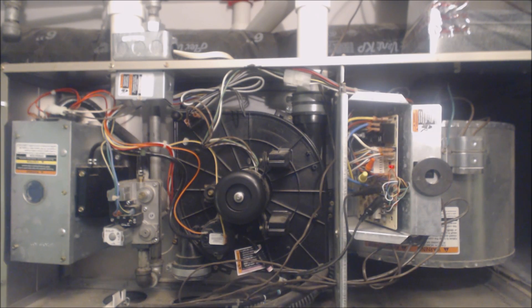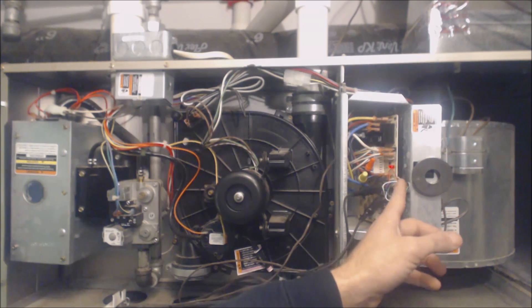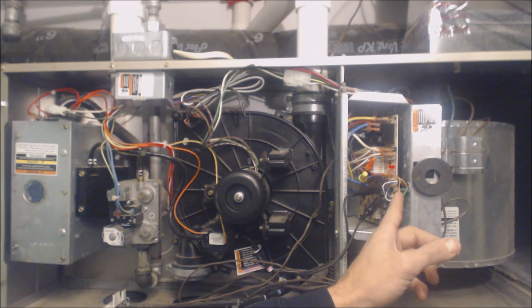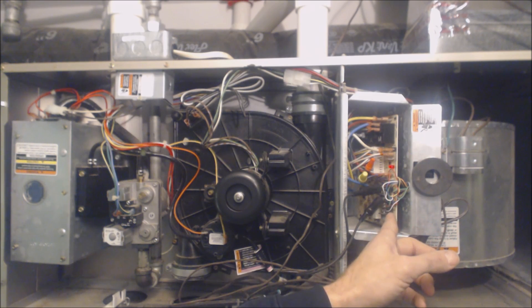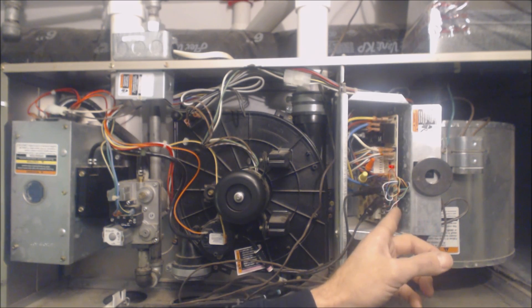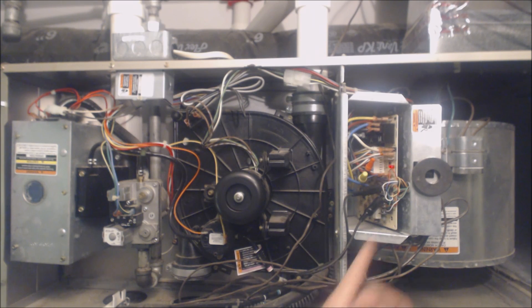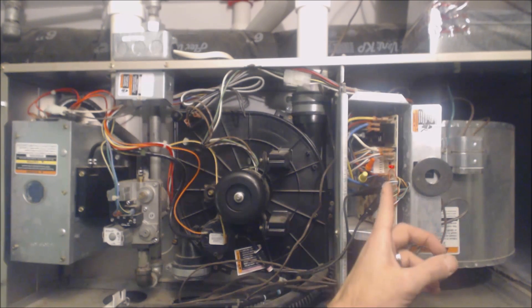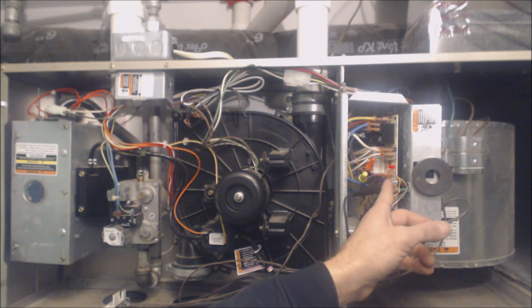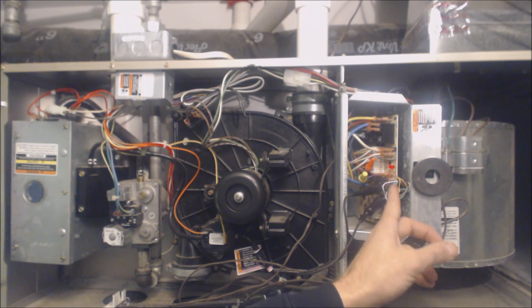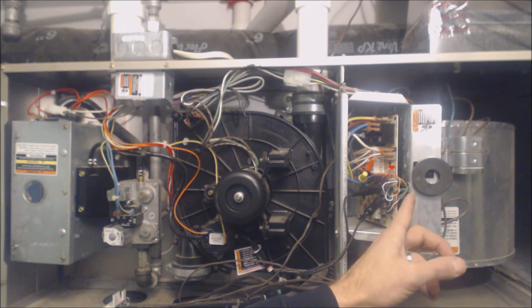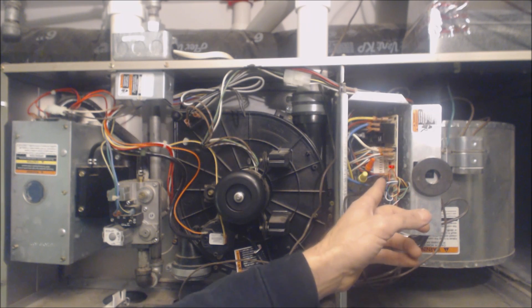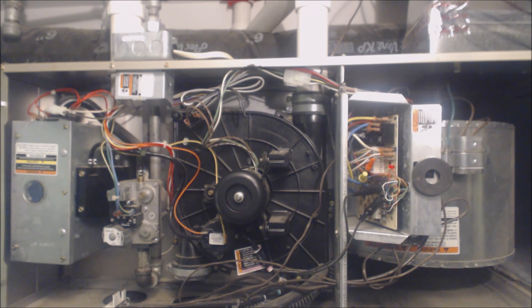If that fuse was blown, that would mean that the R or some type of power wire is touching the C, the wire off of the C terminal. So in the thermostat, turn heat on, R touches W, it comes back through the white wire, but if somewhere along the line W and the wire coming off the C, which is blue, touch, that will pop that fuse. So then you have to diagnose that.